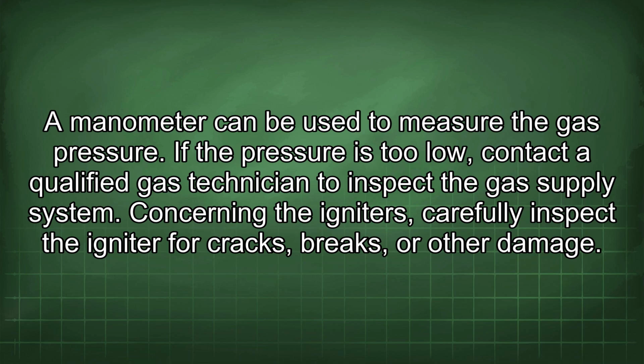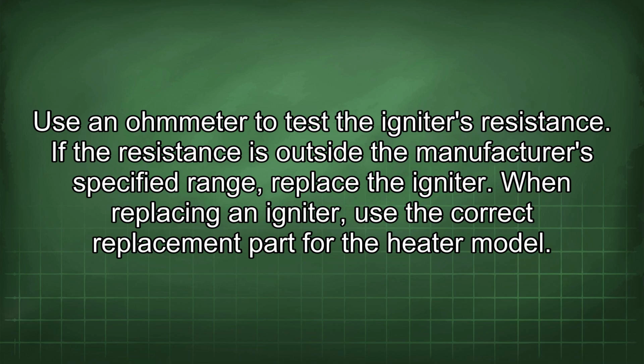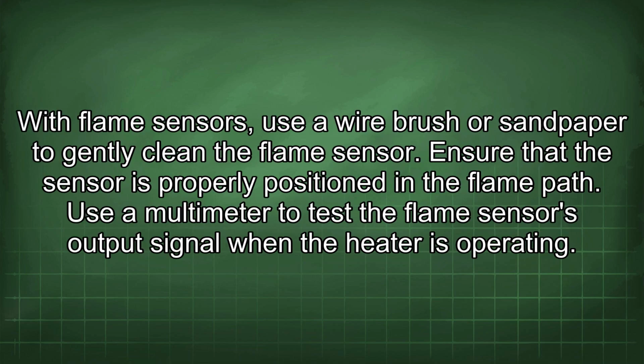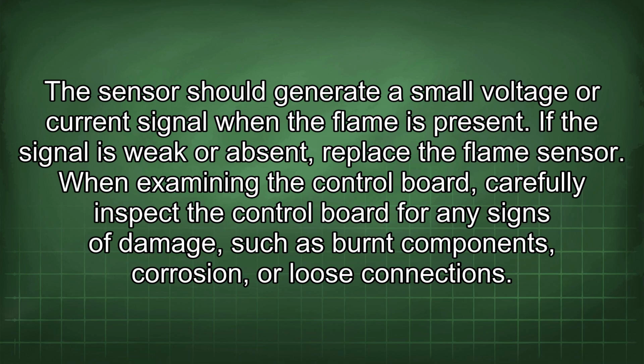Concerning the ignitors, carefully inspect the igniter for cracks, breaks, or other damage. Use an ohmmeter to test the ignitor's resistance. If the resistance is outside the manufacturer's specified range, replace the igniter. When replacing an igniter, use the correct replacement part for the heater model. With flame sensors, use a wire brush or sandpaper to gently clean the flame sensor. Ensure that the sensor is properly positioned in the flame path. Use a multimeter to test the flame sensor's output signal when the heater is operating. The sensor should generate a small voltage or current signal when the flame is present. If the signal is weak or absent, replace the flame sensor.